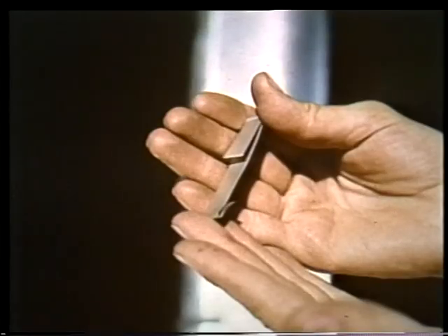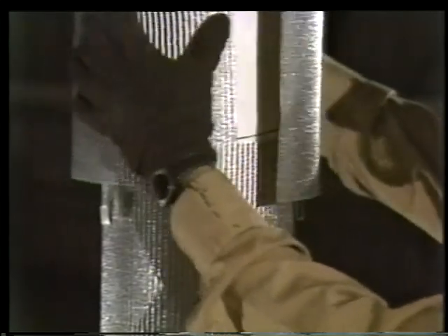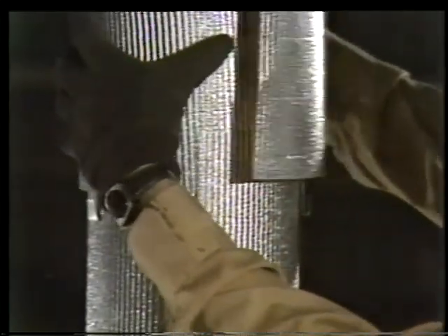Jackets are mounted differently on vertical runs. To keep the jackets from sliding down the pipe, 3 S-clips are hung on the jacket below. The clips are made from scrap pieces of band, bent sharply at either end. The jackets overlap just as before. The clips support the weight of the jacket.